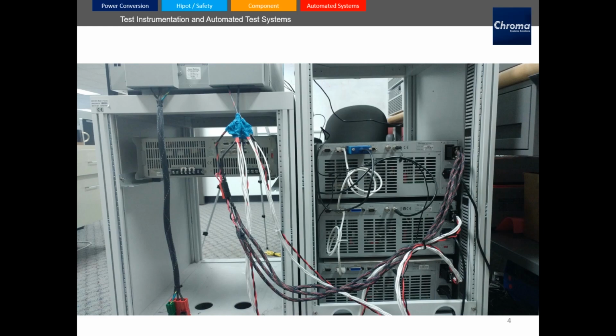For a single-phase configuration, we'll connect all the loads in parallel to a single phase on the power supply's AC output. All the units will also share a common neutral connection.